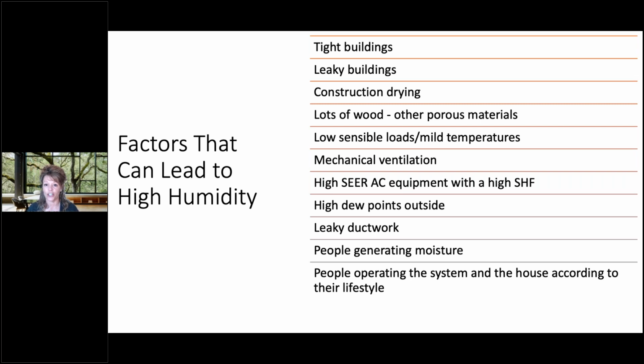Construction drying is a huge one. You can get a couple thousand pints or pounds of moisture just from a wood-built home that is going to have to be managed for several years before it actually dries out. And you're only drying if you've got something to dry that home. So lots of wood. We have low loads, mechanical ventilation, high SEER equipment, high dew points outside, leaky ductwork, people generating moisture.